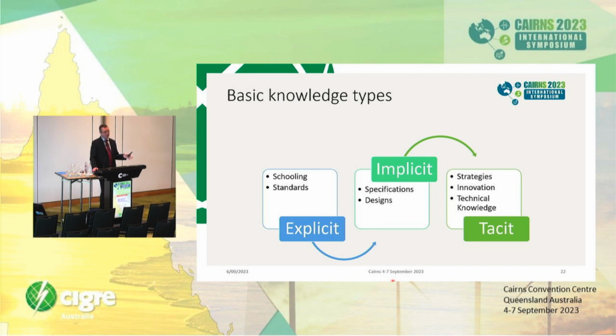And you're a person who can look at a drawing and immediately see, okay, hold on, there's something wrong here. You look again and say, yeah, there's not enough clearance on the 220 kV transformer. Likewise, you could go to site, look at an installation, and say, hold on, something's wrong here. Looking more carefully, you say, oh yeah, there's a phase-to-phase or phase-to-earth clearance issue between the phase and the pipe from the conservator and the transformer, or something like that.